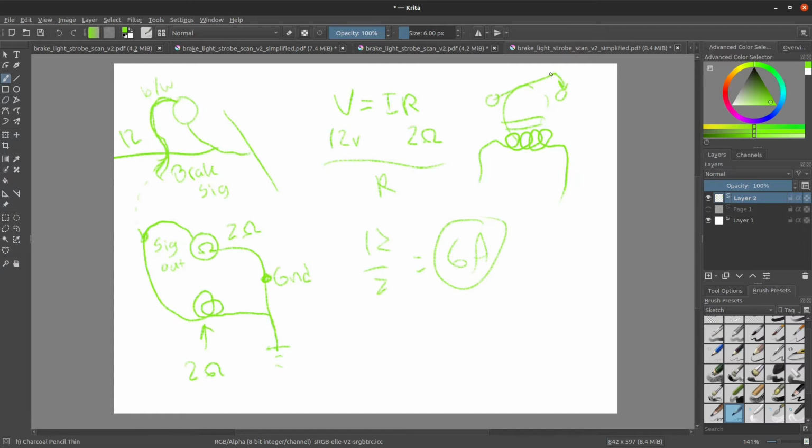When that strip makes contact with the contact, there's a large inrush of current, and that creates another magnetic field around this, which might interfere with the magnetic field from the coil and push the contact back up again.